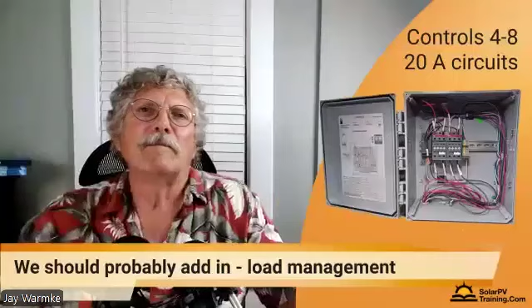But so different things. Now, one thing that I didn't have in that diagram that I probably should have incorporated is load management, because load management is where some of this gets more complicated. The picture here is the Enphase load management device. And you can have up to 2 of these with each of your smart switches. And so it can control 4 to 8 circuits. So in this case, this is showing you what is essentially 4 single pole or 2 double pole circuits.